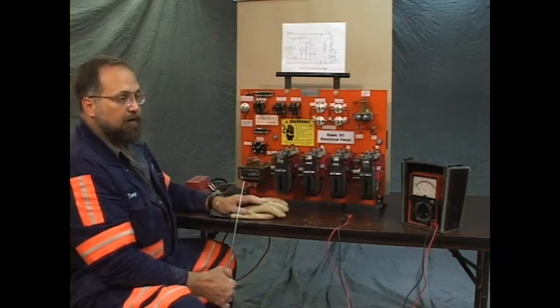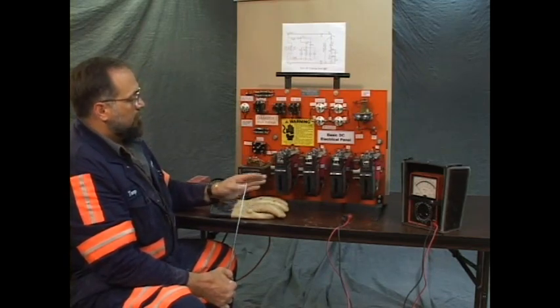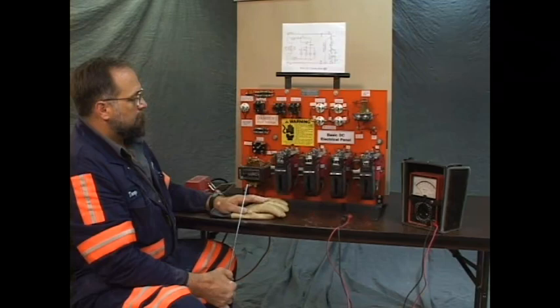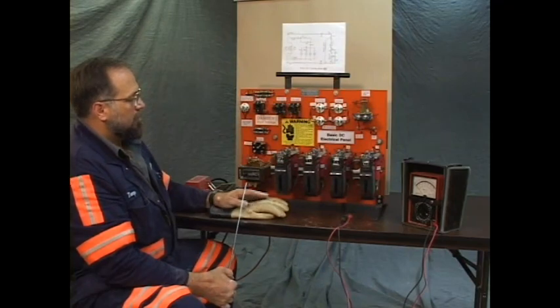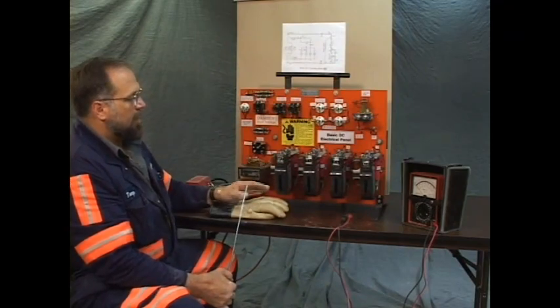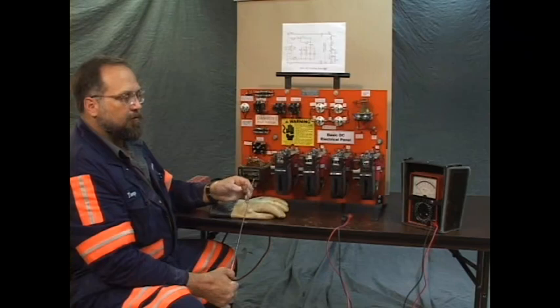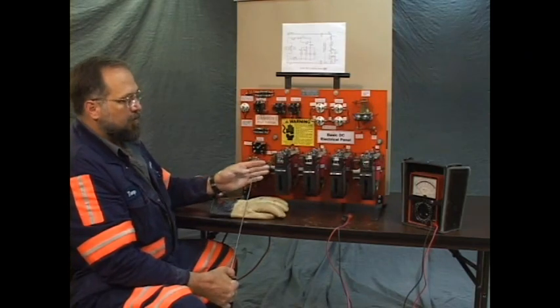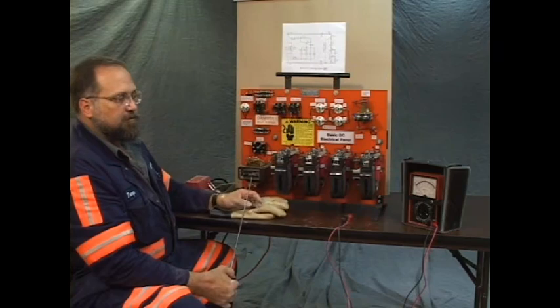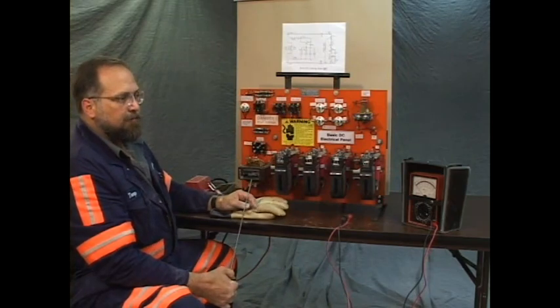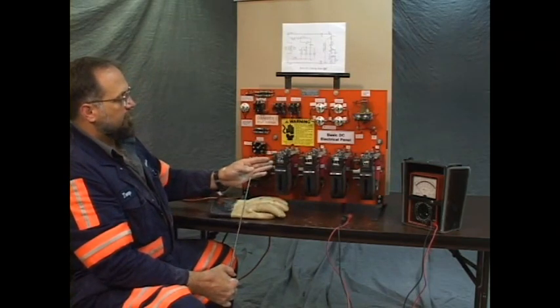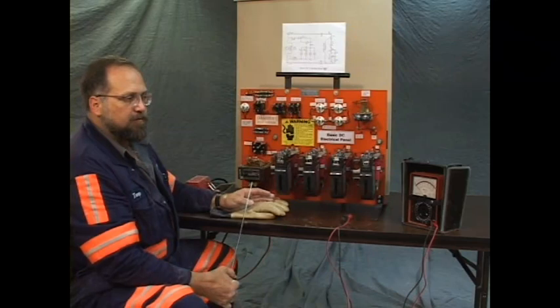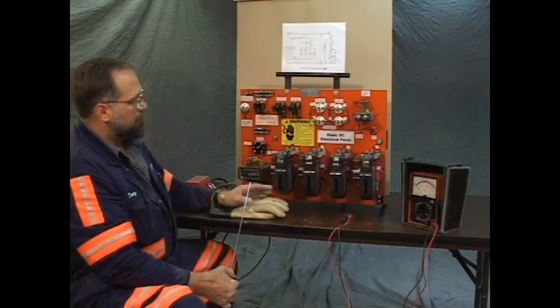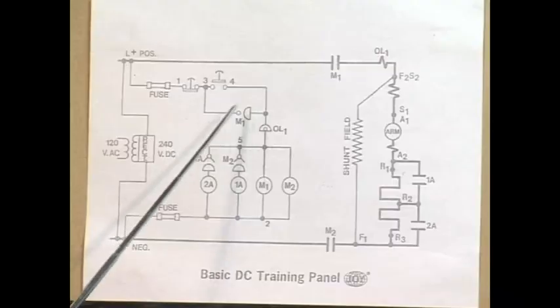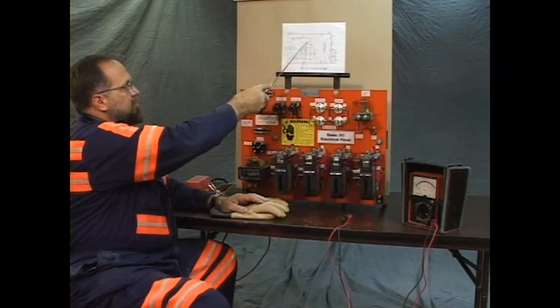It's a liquid metal, and you can use it as a timer by the magnetism drawing the mercury through various size orifices, openings to fill a vessel and close a circuit between two contacts. This one, though, is not a timed circuit. It's an instantaneous. It's normally open and instantly closed.